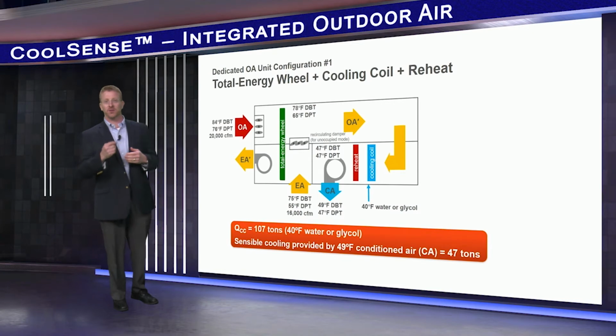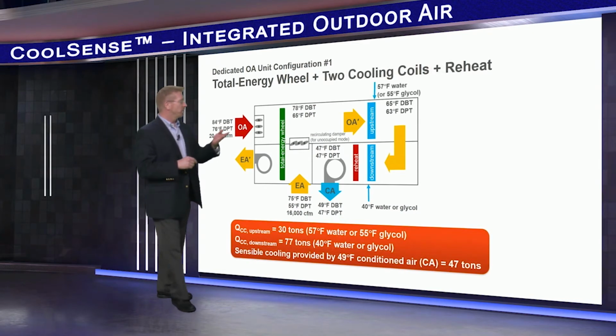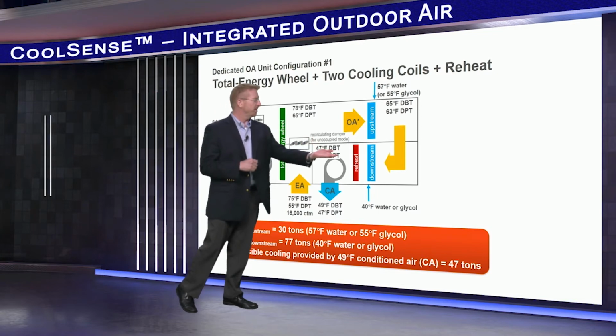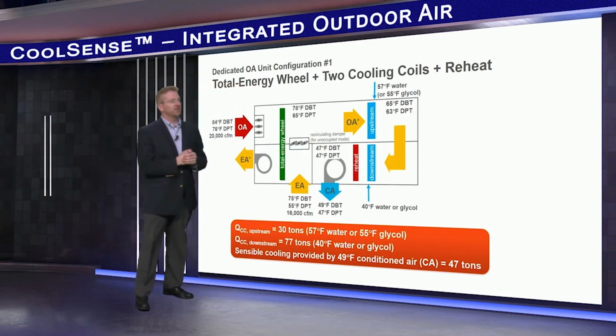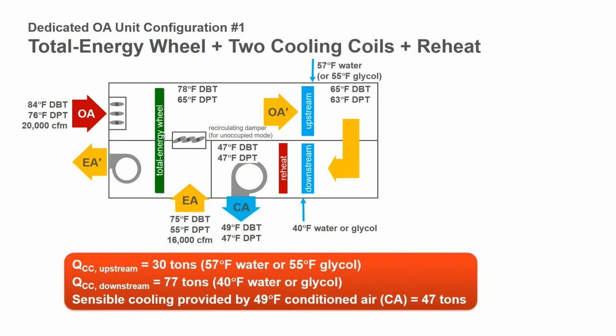Next, we'll look at a simple enhancement to this configuration. Now, focus your attention right here. This is the same air handler, but now it has two cooling coils in series instead of just one. The same 49-degree leaving air, same 107 tons, but now this capacity is divided between two coils. The downstream coil receives the same 40-degree water needed to achieve the 47-degree dew point, but the upstream coil can receive warmer water. The chiller plant is sending 57-degree water to the sensible cooling coils in the CoolSense terminals. By adding this upstream cooling coil, we can shift 30 tons of load to the warm water chiller.